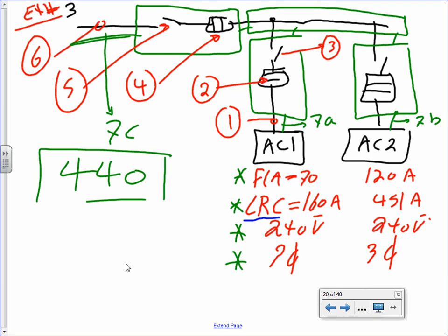Okay, here's what we have. I have two chillers. The reason you will highly unlikely have this example, guys, is that typically if you have a chiller, it's fed directly with its own branch circuit. Each one of them has its own disconnect, overcurrent protection device and branch circuit, as you can see. They're both fed from a gutter and through a fused disconnect. And again, I have my feeder coming into it. The feeder should be on the other side, but not a big deal.